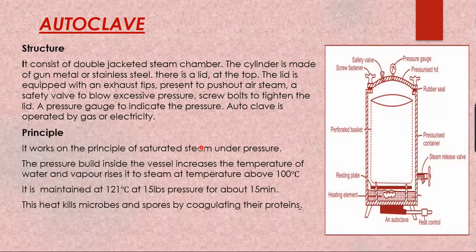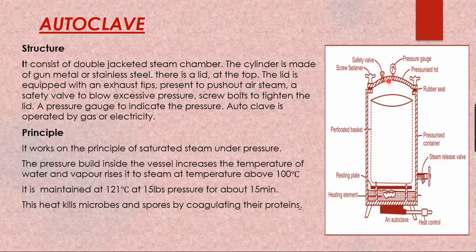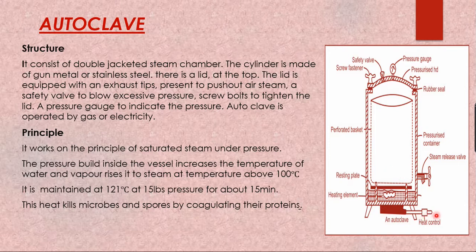Looking at the structure of the autoclave: it has a double-jacketed steam chamber. The cylinder is made of gunmetal or stainless steel. The lid covers the top and is equipped with an exhaust to release excess steam and a safety valve to blow out excessive pressure, screw bolts to tighten the lid, and a pressure gauge to indicate pressure. The autoclave is operated by gas or electricity. Its working principle is saturated steam under pressure.